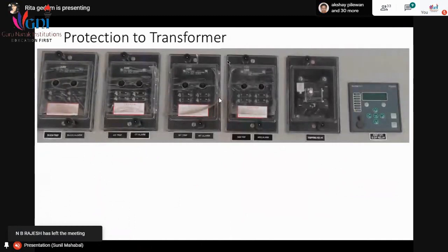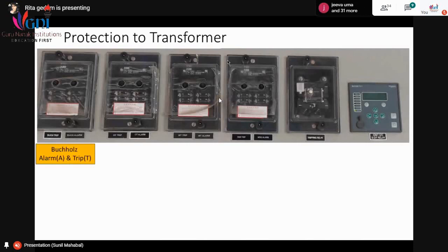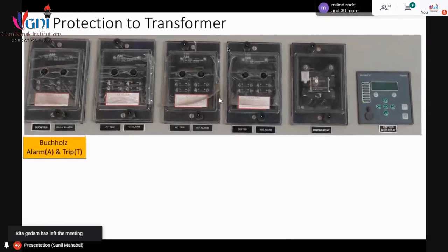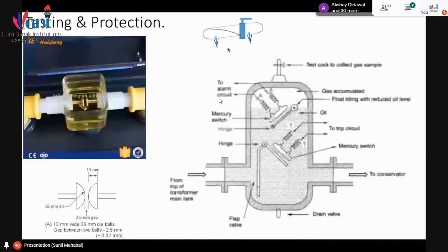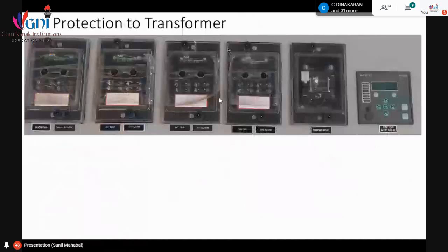You may not be able to read it, so I have provided the tags here. This is the Buchholz alarm and trip. It will give you an alarm as well as a trip signal. The upper mercury switch, the one on the top, is for the alarm circuit. And the mercury switch which is immersed in the oil is for the trip circuit. So there are two distinct mercury switches meant for the alarm and trip circuits. So this is how the Buchholz alarm as well as the trip circuit works.